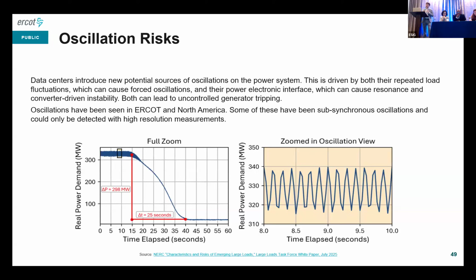The tricky part is you have to keep up with the controls and continuously review them, because if you change the load profile or the technology at the back end of the data center, what was once true may no longer be true. These facilities replace hardware every few years, constantly upgrading equipment, so keep that in mind as you write your definition of a qualified change to your facility.